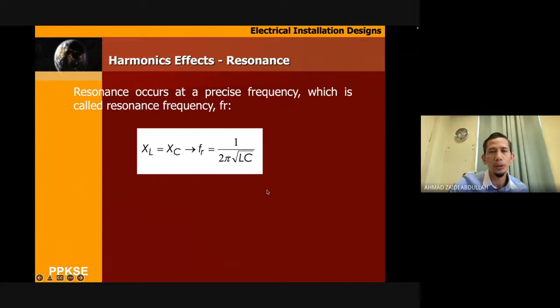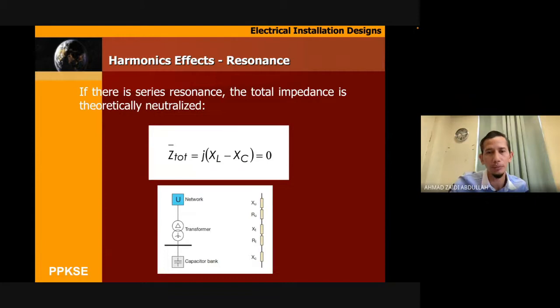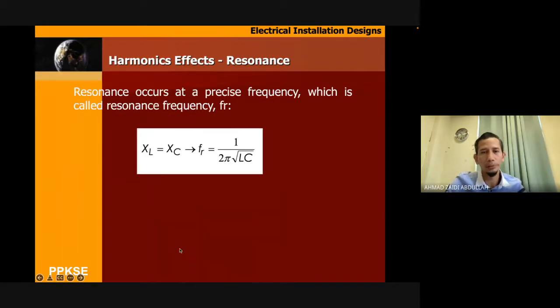If you can see from here, okay, you can see here. This is how we connect the capacitor bank. So from the bus bar, from the network, we have a transformer, and from the transformer we have a bus bar here, and then normally we connect the capacitor bank directly to the transformer or bus bar.